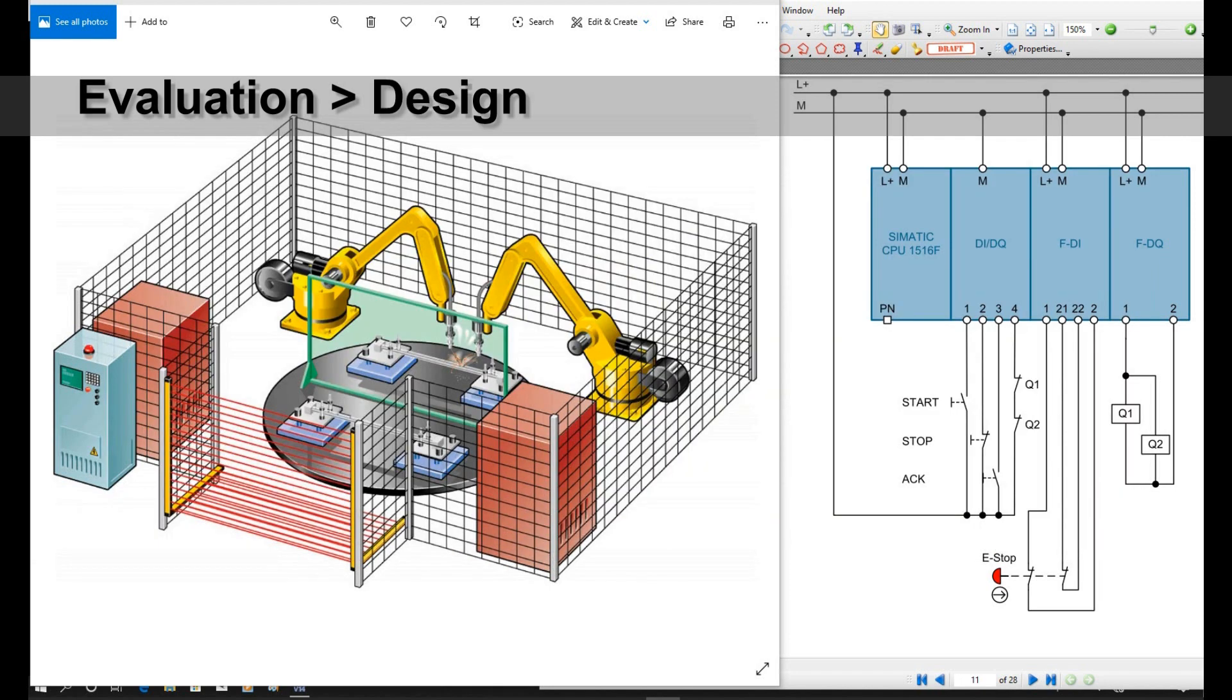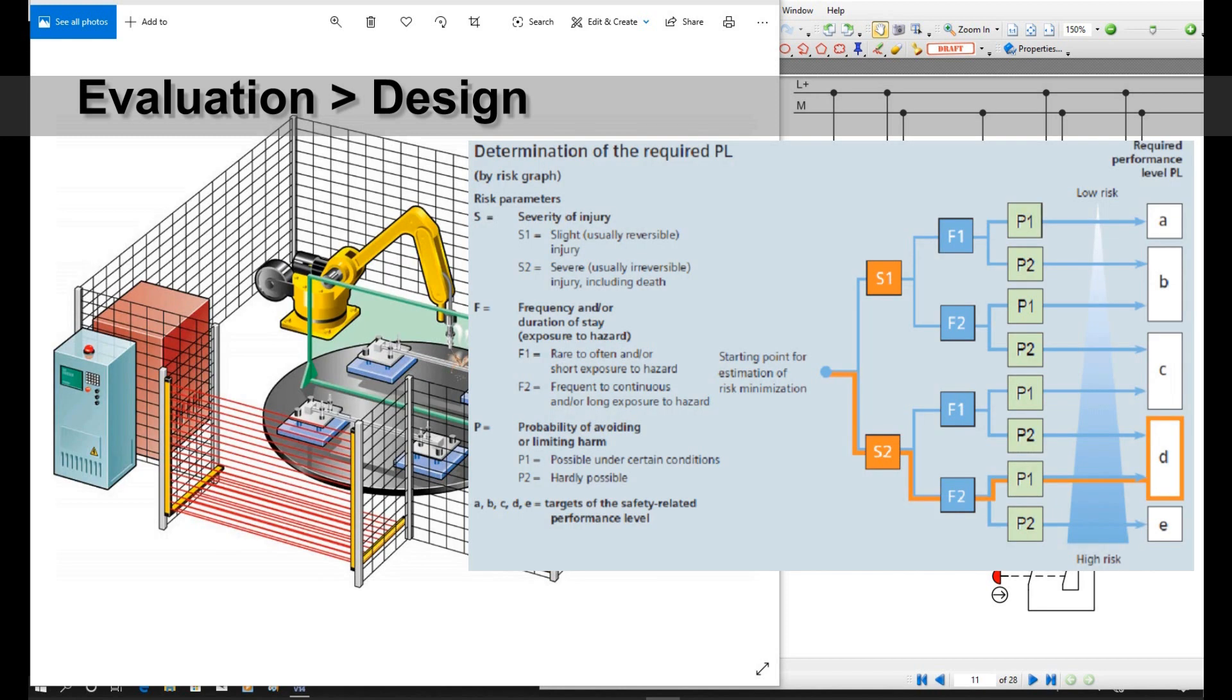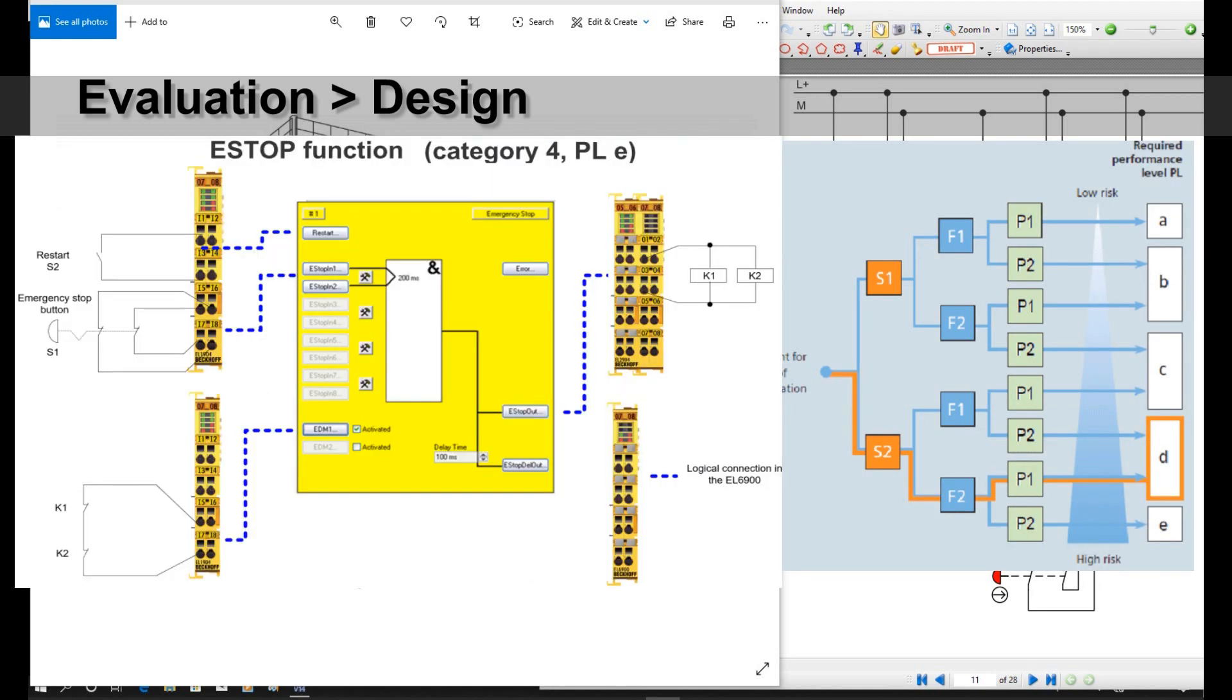When we talk about the design, as the pictures shown in the video on the right side, usually for the designer, they need to think about how to guarantee the safety level. For example, the Category 3 or Category 2, based on the risk evaluation, what kind of safety circuit you need to design that can reach that safety level and guarantee people's safety.